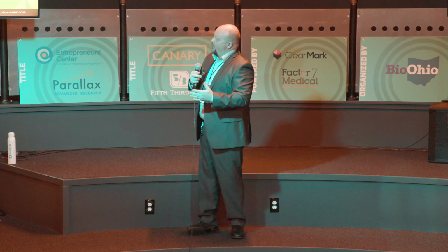What this customer was doing, they were doing a lot of manual testing of flexing the device and then taking inspection images and seeing how that flex compared to what it should have been. So a lot of manual comparison testing. The other part of that was they would come in and they would take electrical probes and touch the tip of the device to prove that it made a circuit or that it passed its electrical functions, which is all perfectly fine. But that whole process was 15 different operators or steps where they needed to walk the product, and it took 20 minutes to complete one device.